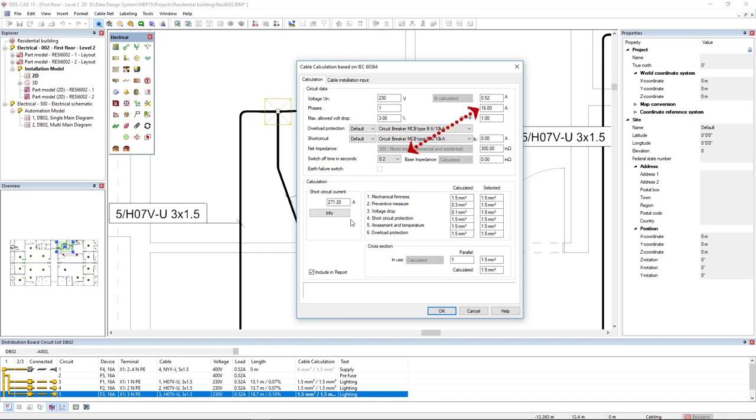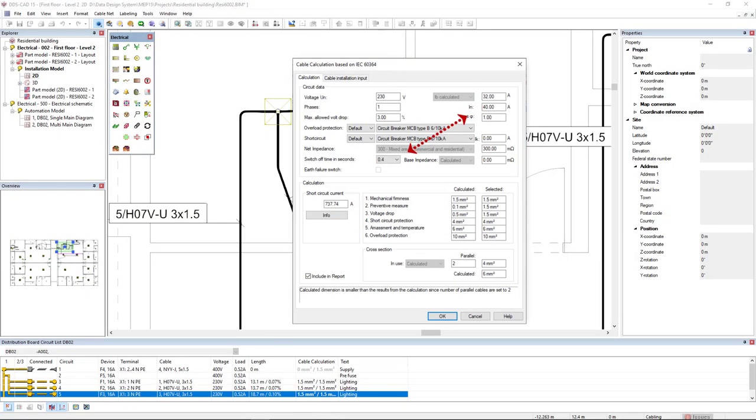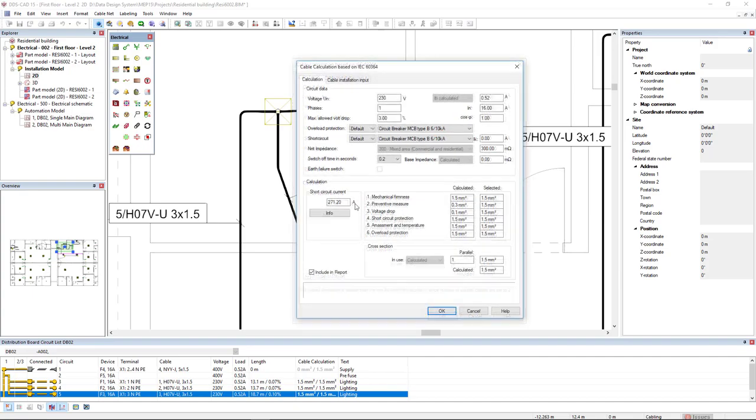Depending on if a circuit's Ib is less or more than 32 amps, the switch-off time will be set to 0.2 or 0.4 seconds automatically.